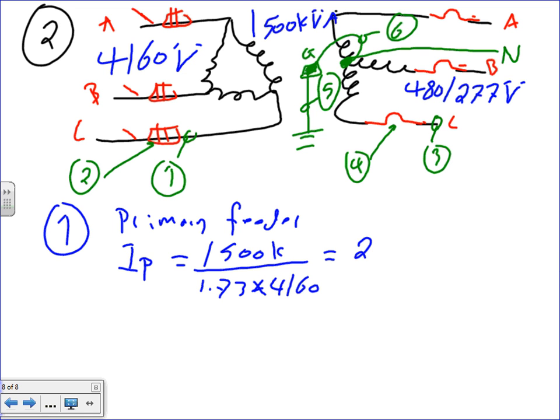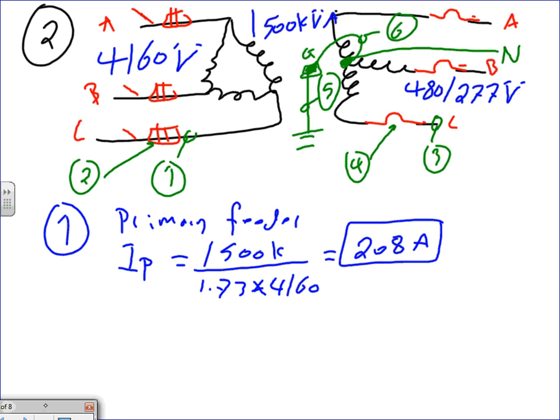If you do that, you're gonna end up with 208 amps. Then you're going to take, again, this is debatable, but let's just continue doing it because smarter people are doing it, 1.25 continuous load multiplied by 208. And you come up with 260 amp.